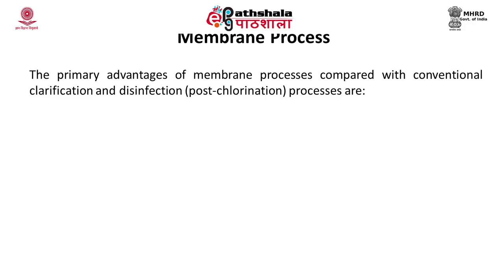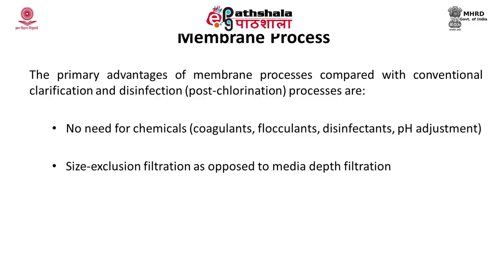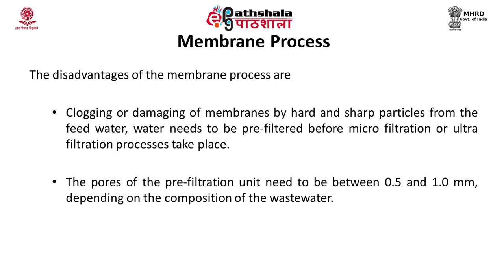The advantages of membrane processes include no need for chemicals like coagulants, flocculants, or disinfectants — unlike other processes where chemicals are added to water. The second advantage is size exclusion filtration, and the process is simple and automated. The drawback of membrane processes is potential damage to the membrane by hard and sharp particles from the feed water, so the water needs to be pre-filtered before membrane treatment, and the pore size of the pre-filter can be adjusted depending on the composition of the water.